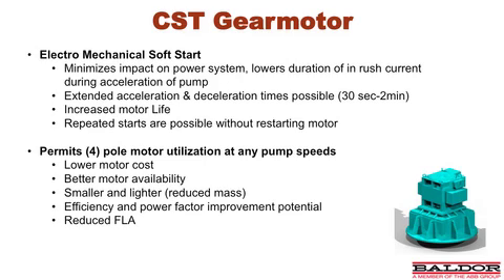We also provide a 4-pole motor as opposed to a high pole count motor. Using a standard 4-pole motor and the gearbox, we can provide whatever speed the end user requires for their application. The 4-pole motor provides lower motor cost, better motor availability, smaller and lighter reduced mass, and higher efficiency and power factors, as well as reduced voltage, or full load amps, I should say. A little bit about how the system reacts relative to your current configuration, and then we'll discuss how it is impacted with the CST gear motor solution.